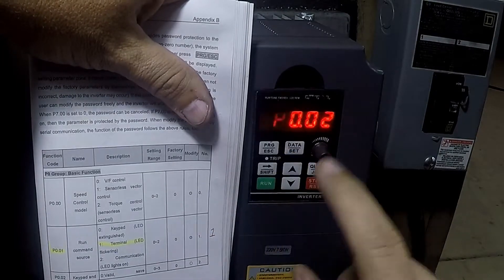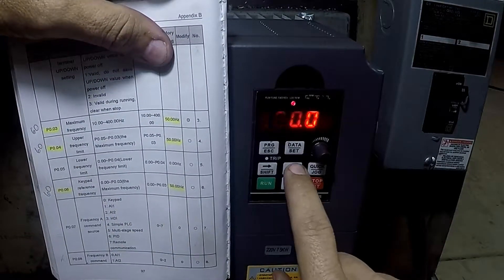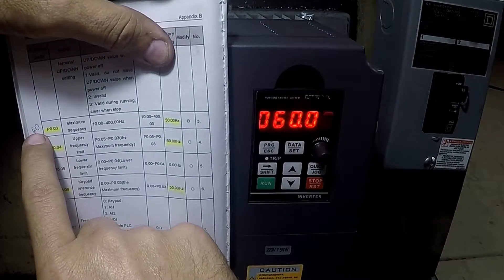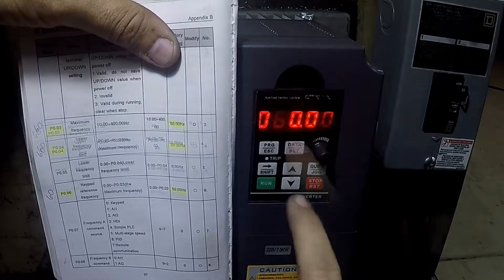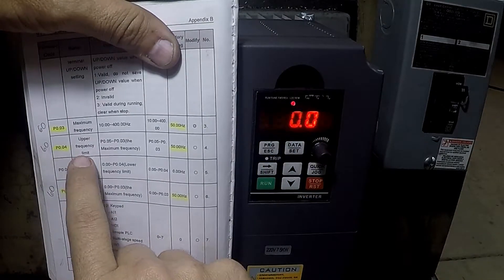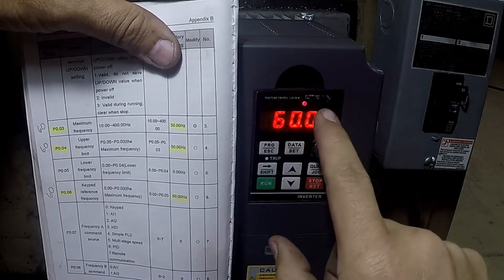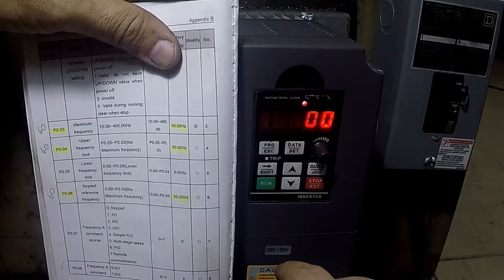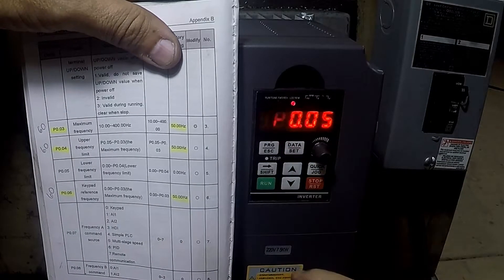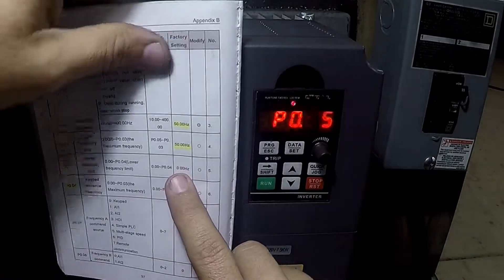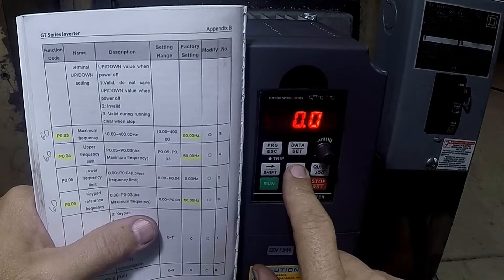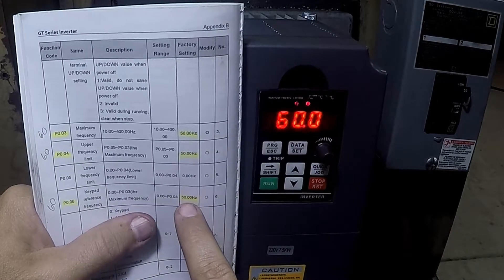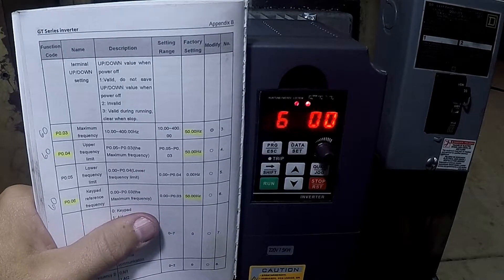Here we're going to skip to P0-3, so I'm going to go up to three. I'm going to hit set and this one defaults to 50 but I've set it to 60. When you set a parameter it'll automatically jump to the next one for you. So this one should also be set to 60, which it is. P5 is lower frequency limit which defaults to zero and I didn't need to change that one so I left that one alone. P0-6 is set to 60, changed off of its default of 50. That's the keypad reference frequency.